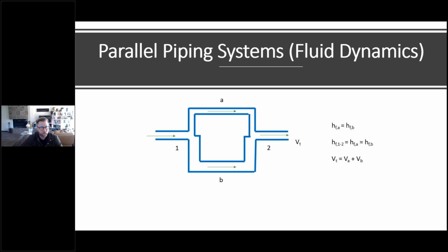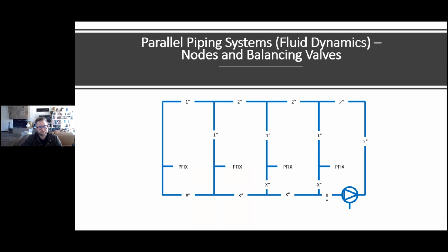Now, the other thing we could do is increase the flow through A by increasing the pipe diameter of A, or we could introduce a pump into A. The only worry if we introduce a pump to A is we would probably want some kind of check valve on pipe segment B to prevent the flow from just going in a clockwise circle there. So got to be mindful of some of the hydraulics there, but in general, modifications to B is what we're looking at. Now, most of our plumbing systems don't just have 2 parallel branches, they have more than that.